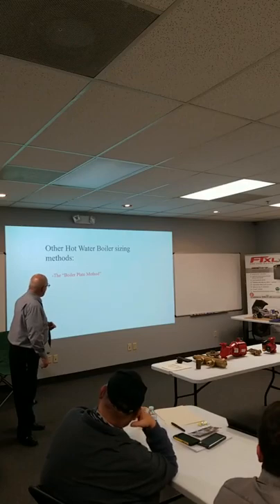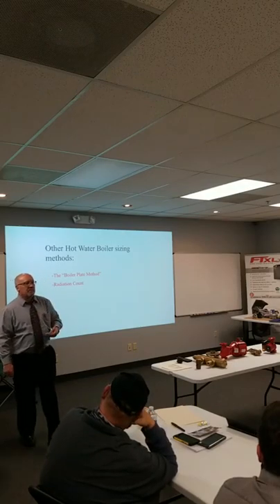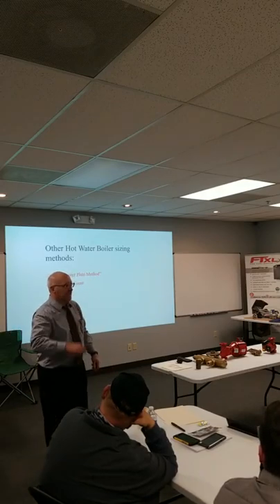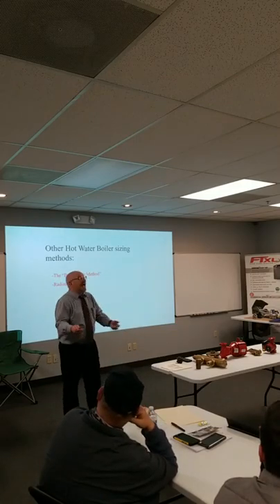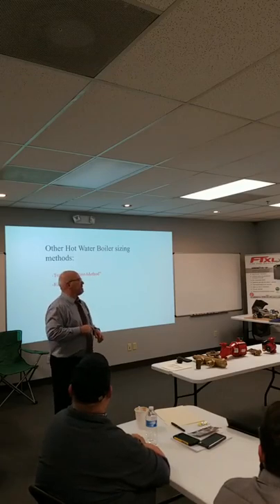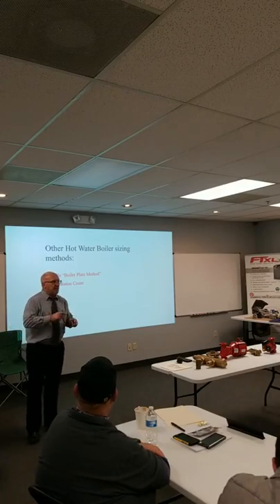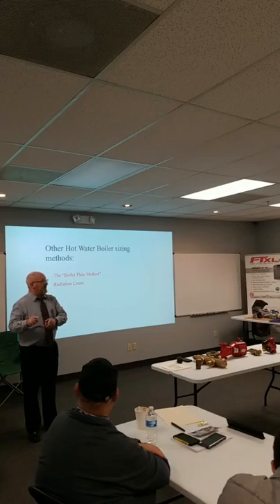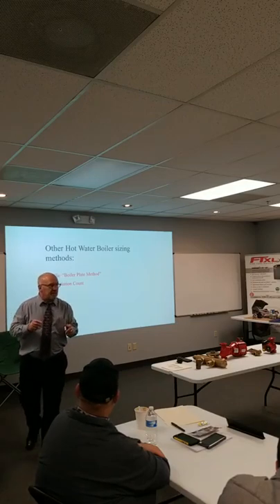So the boilerplate method, probably the most common. Radiation count. How many say, I'm going to go through the building and count my feet of radiation? We do it, right? I'm going to ask you to do that, but I'm going to ask you also to do a heat loss. And I'm going to show you why. Counting radiation doesn't mean the size of the boiler. It means what water temperature you're going to need to satisfy the heat loss. So counting radiation really doesn't mean much for us.